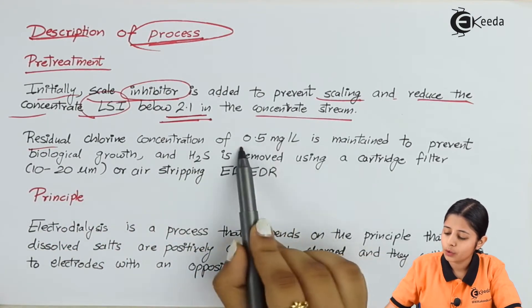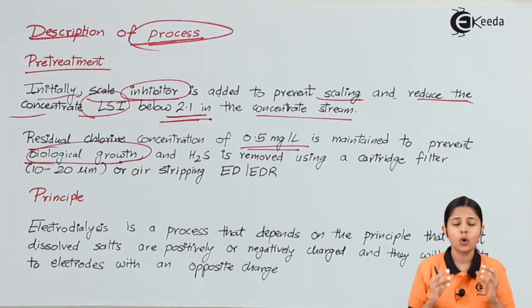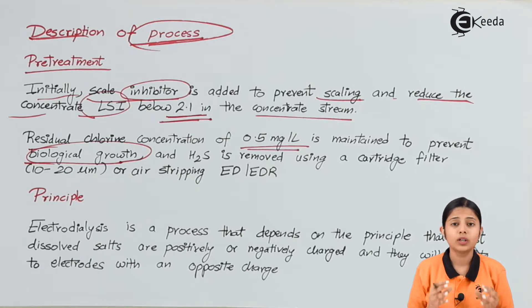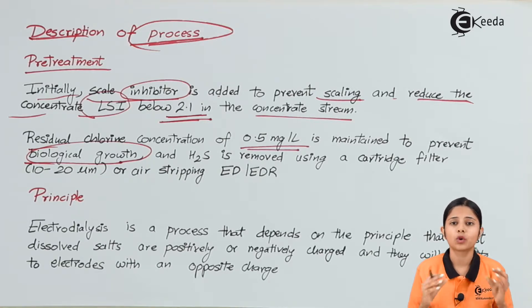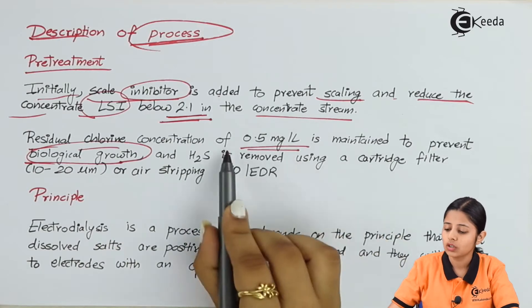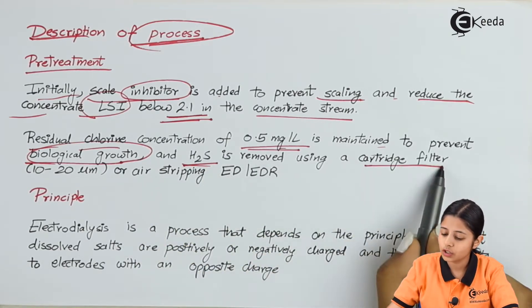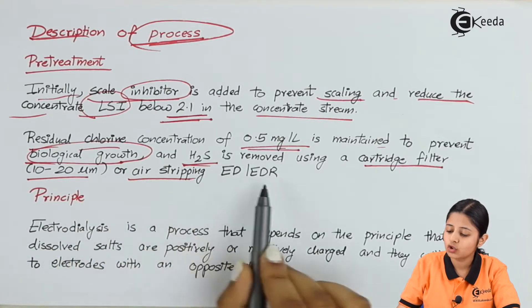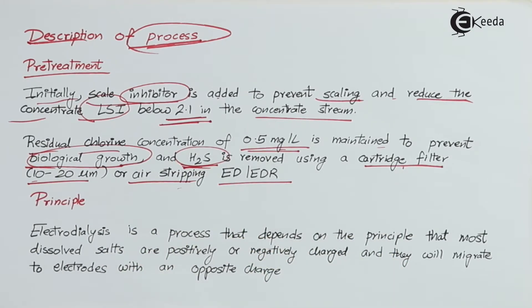A residual chlorine concentration of 0.5 mg per litre is maintained to prevent biological growth. Microbes, bacteria, and certain viruses grow in water because water (H2O) contains oxygen, which supports microbial growth. By maintaining chlorine at 0.5 mg per litre, biological growth is suppressed. Additionally, dissolved hydrogen sulphide (H2S) is removed using a cartridge filter of 10 to 20 µm, or by air stripping in ED or EDR processes.